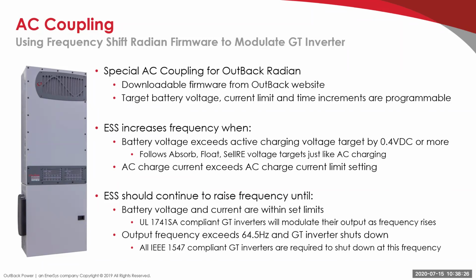And if you have a UL 1741 SA, that's the supplemental addendum to 1741, that hasn't turned into an IEEE spec like UL 1741 turned into IEEE 1547, there will be a forthcoming IEEE standard. But right now, there's California Rule 21. There's actually at least 2, if not 3 flavors of that. And then Hawaii has their HECO, the Hawaii Electric Company, has Rule 14. And so they have these grid support conditions that allow the grid to be supported.